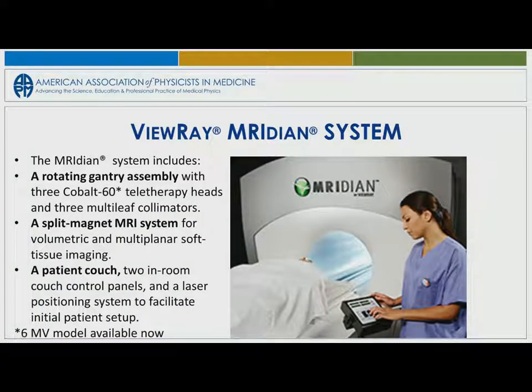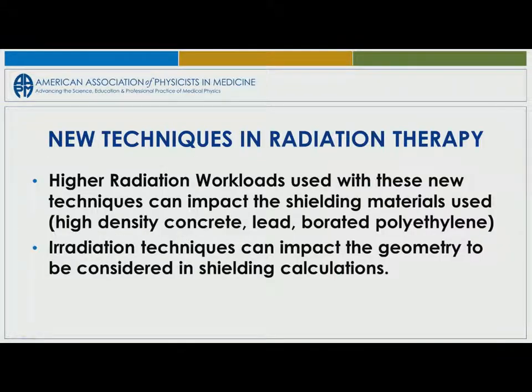Now, the fun has begun because we've now combined MRI with treatment units. When I put this slide together in December, the Viewray system that was available was the one with 3 Cobalt 60 units in it. That's what's installed at UCLA. That's the one I'm familiar with. But what just got approved by FDA is the one that now has the 6 MV LINAC in it. So you are now shielding a 6 MV LINAC, and your MRI shielding has to be in that vault. And no, there's not 3 LINACs in it, there's only 1 LINAC in it.